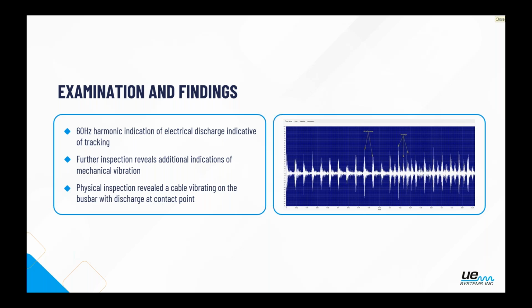And this is a good example of seeing two events occurring at the same time. So we have 60 hertz line frequency. If it looks familiar to you on the left, that's that impact and ring down. Something's mechanically loose. But then we also see that discharge pattern, possibly tracking and arcing, or just tracking, at the same time. Definitely more than one thing happening at once, and the more information we can give to the team that's going to this equipment, the better they are at knowing what to look for.